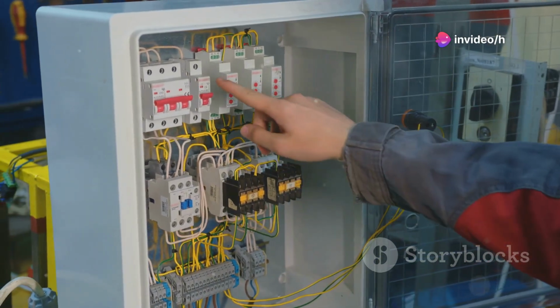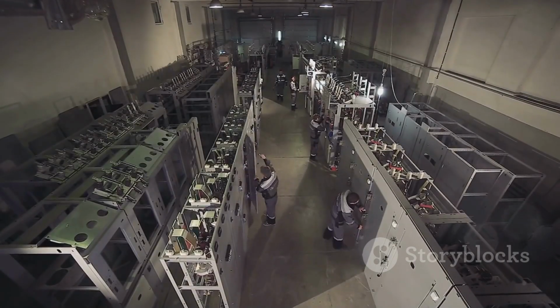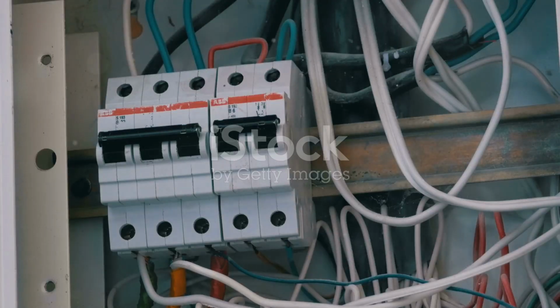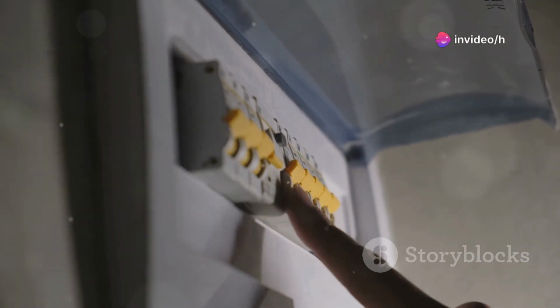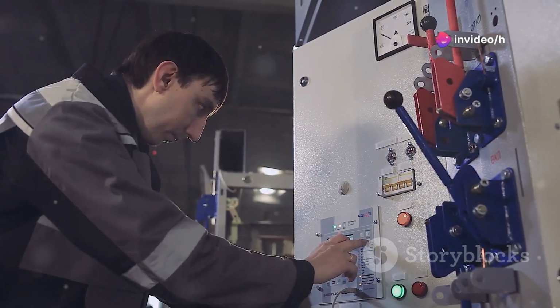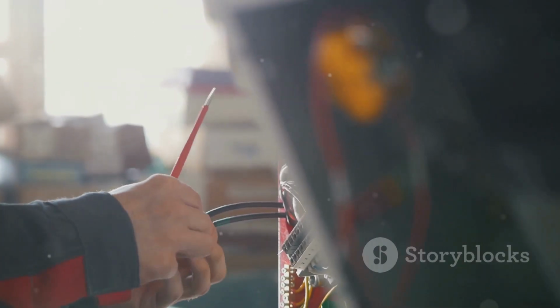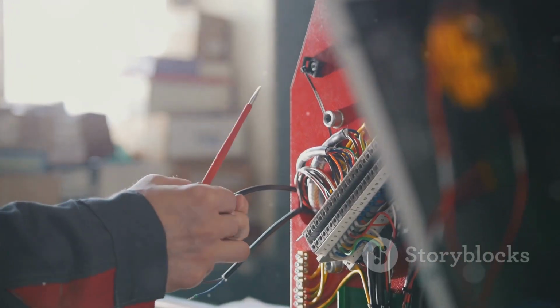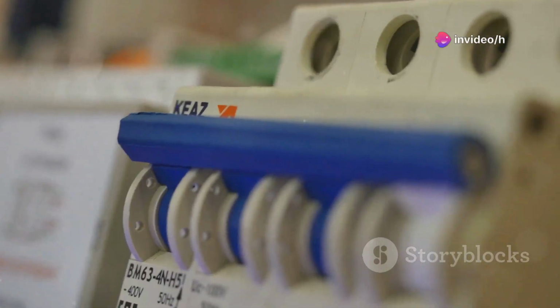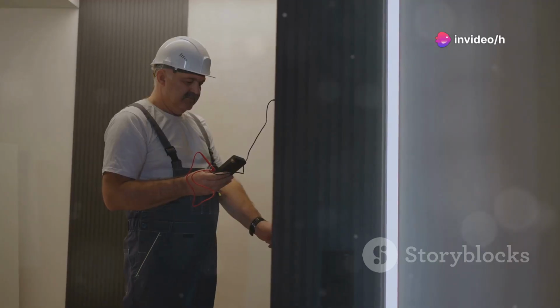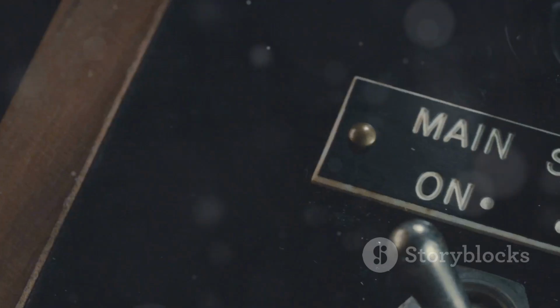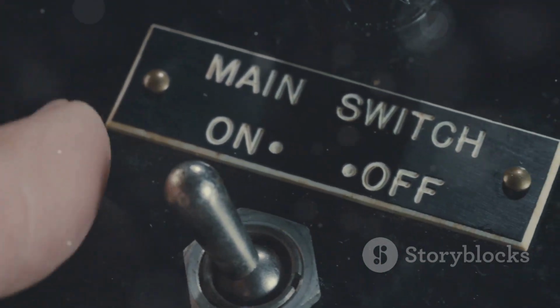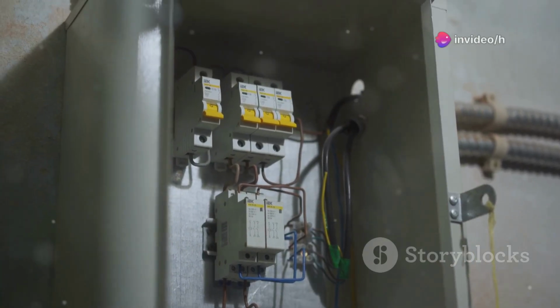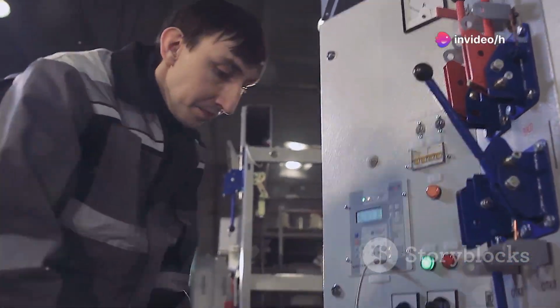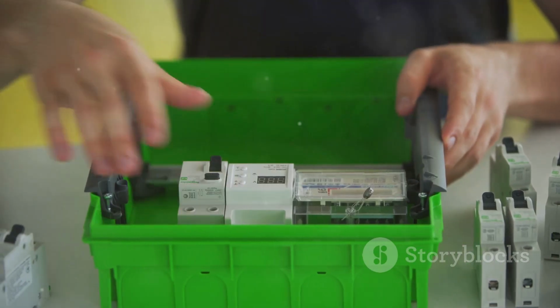Now let's wire the emergency power switch. Stay sharp, this is critical. Power outages can halt production and create hazards. A changeover switch lets you safely switch between city power and a generator, never connecting both at once. Install the switch in a prominent spot in your panel. Wire city power to one set of terminals, generator to another, and outputs to the panel's main bus bars or RCCB. The switch's design prevents dangerous backfeeding. Double-check all connections. Mistakes here are costly and dangerous. In an outage, move the switch from city to off, then to emergency power. When grid power returns, reverse the process. This manual switch is simple, reliable, and essential for any critical operation. Preparation is key. Don't get left in the dark.